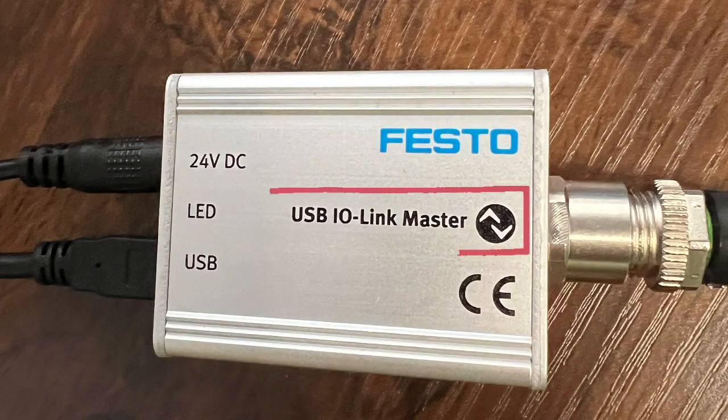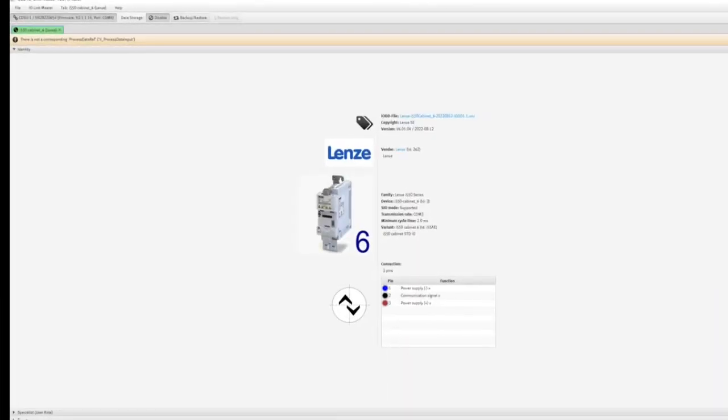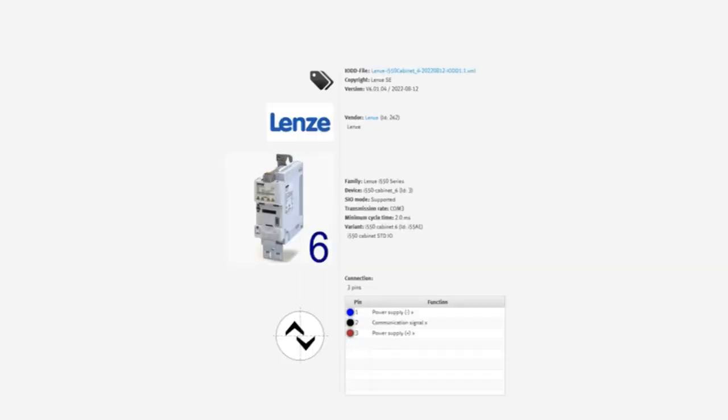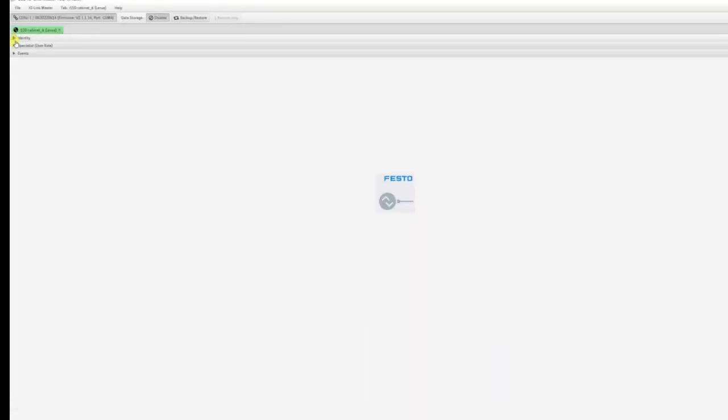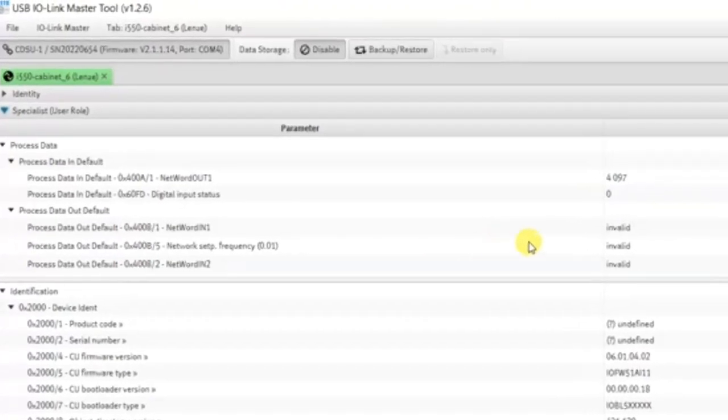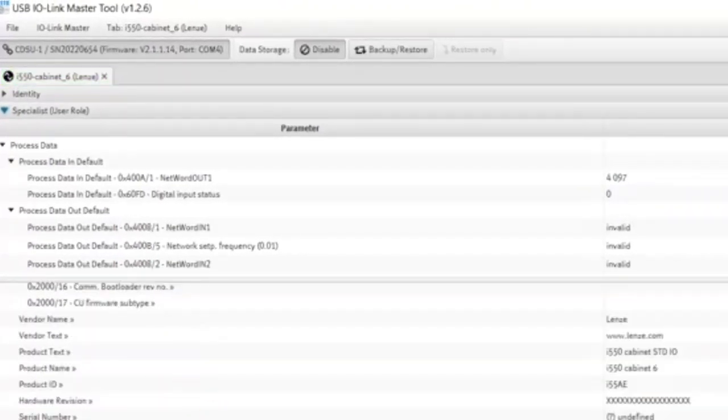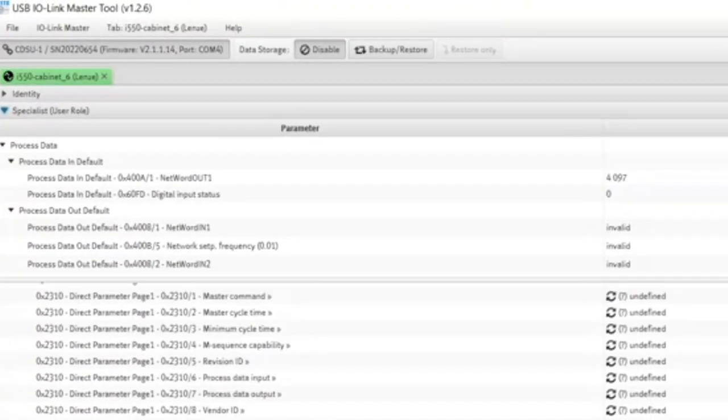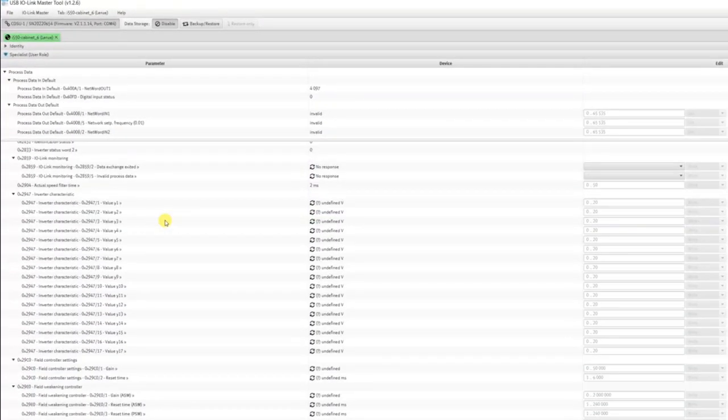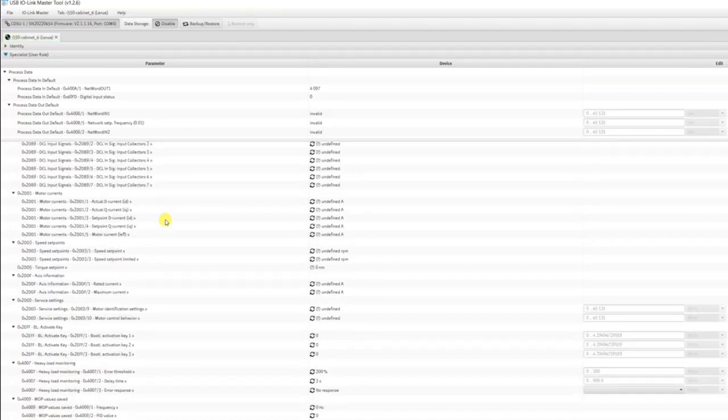I'm going to use the Festo single port CDSU and hook that up to the VFD. What that will do is pull in the IODD automatically, as long as I have an internet connection, and that will allow us to access the parameters of the drive for commissioning. So I'm going to dive in here to some of these parameters and show you how to set it up. A very basic setup, get that motor turning very easily.